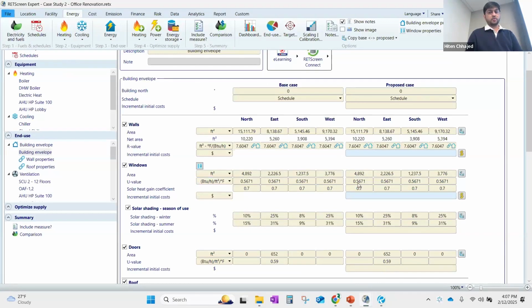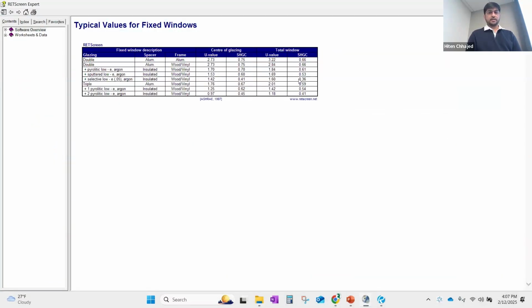So what you will change is the U value, assuming they're the same on each face of the building, and the solar heat gain coefficient, which should also be in this table right here, SHGC, for triple pane low E argon, which is 0.41.